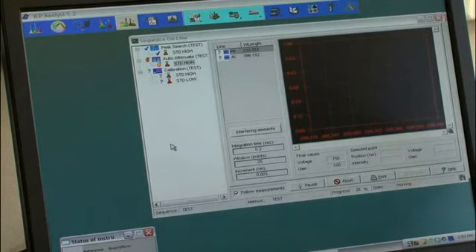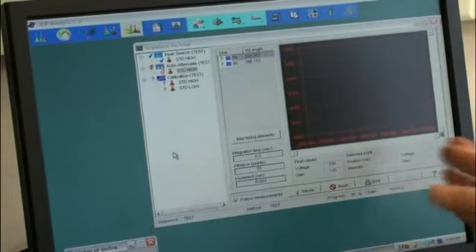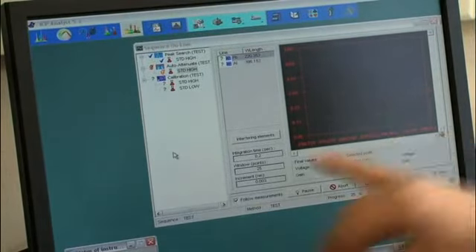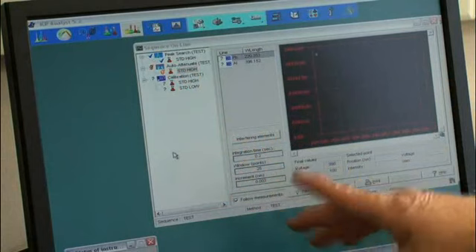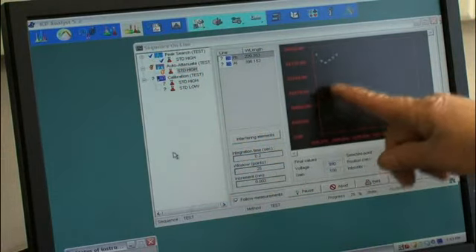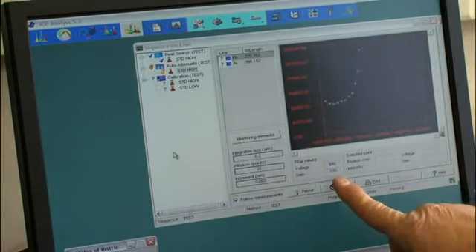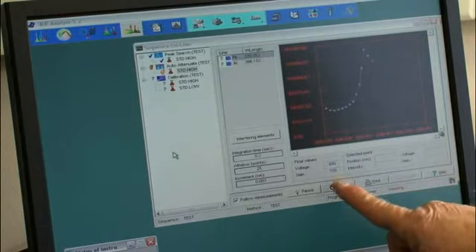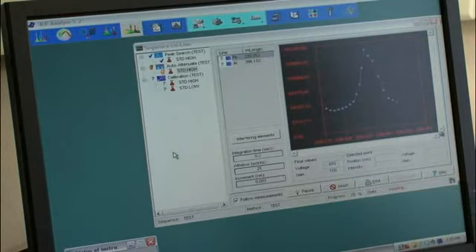so what it did first was a peak search in a small window, didn't find the peak for aluminum, so it went to a larger window. Now that it found the peaks, it's doing the auto attenuate. So what it'll do is it's going to scan, but at the top of the peak, it's going to start adjusting the voltage and the gain. So it's optimizing the photomultiplier for that concentration of that element.